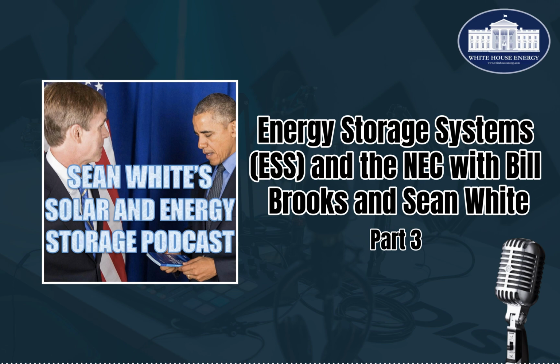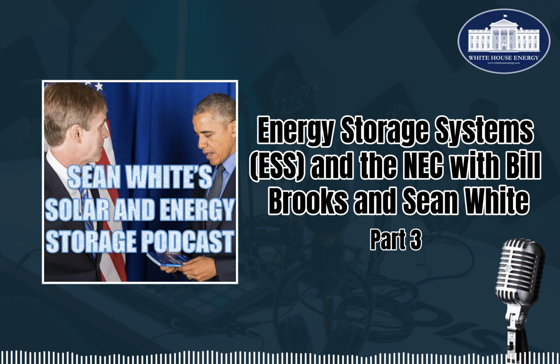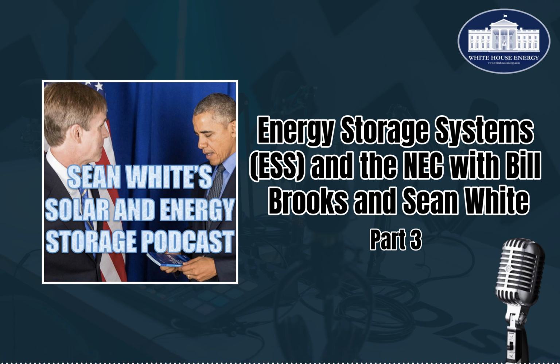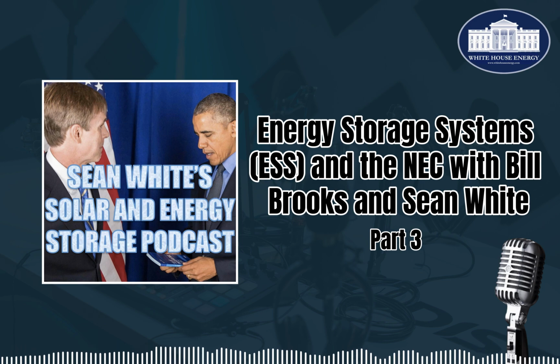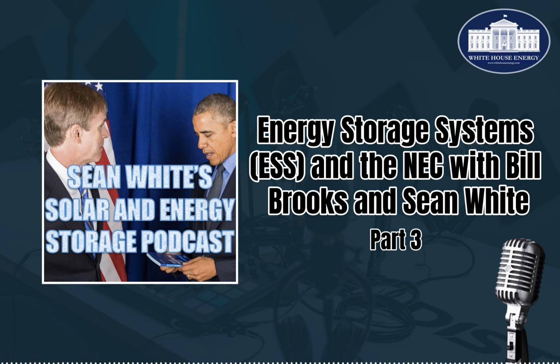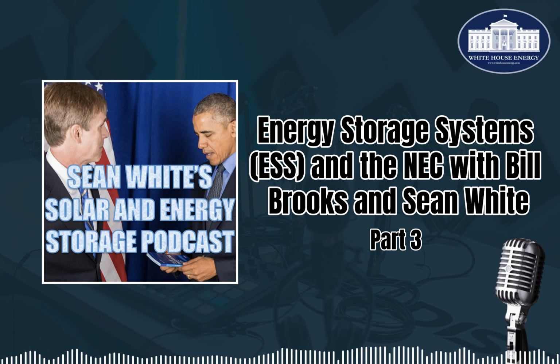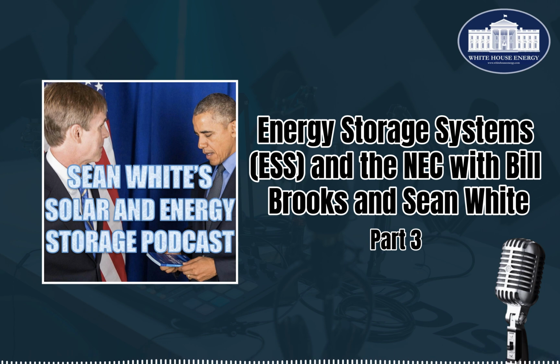I'm sure. Nowadays, we call things functionally grounded instead of ungrounded and grounded like we were before. So if you hear people talking about a grounded inverter or ungrounded inverter, you know they're talking about the 2014 NEC 99.9% of the time. Functionally grounded is a system that has a ground reference that is not solidly grounded. Reference grounded system, low resistance electrical reference to ground. So we could say perhaps that is the fuse grounded system, which is also another type of functionally grounded system.